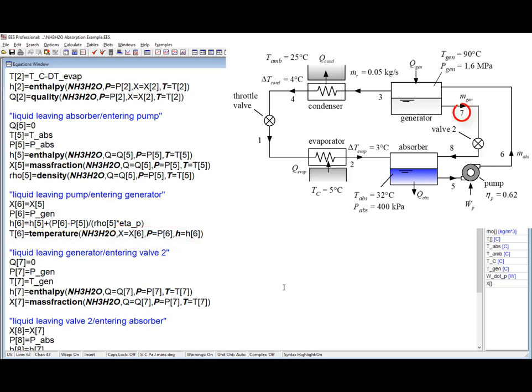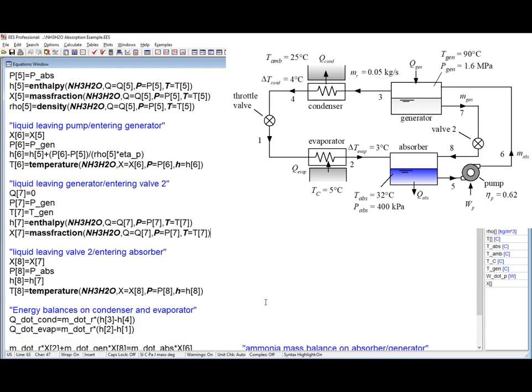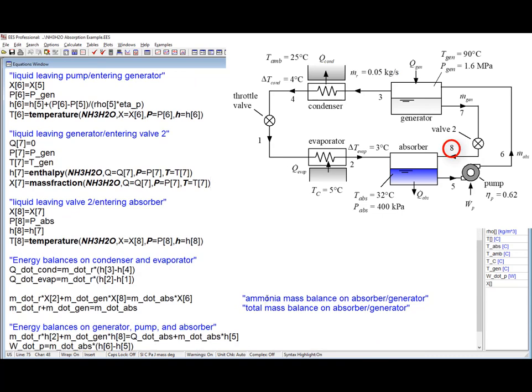The liquid leaving the generator at state 7 is at the generator temperature and pressure and its saturated liquid. So its state is going to be fixed by P, T, and Q. This liquid passes through a valve where it is throttled to the absorber pressure. And the mass fraction and the enthalpy can't change as you flow through that valve. And therefore its state is going to be fixed by X, P, and H.